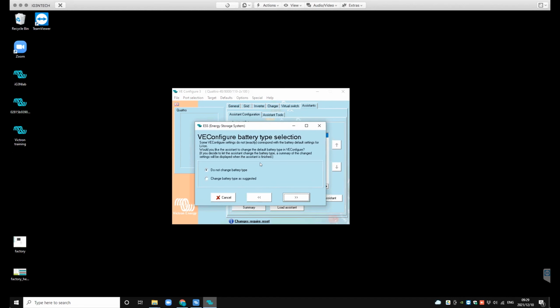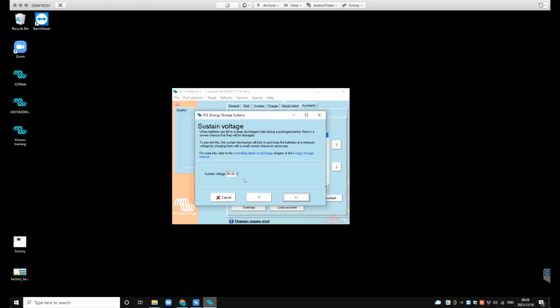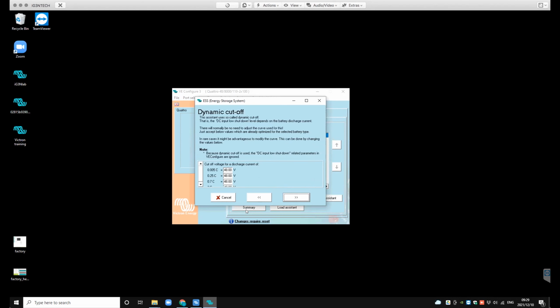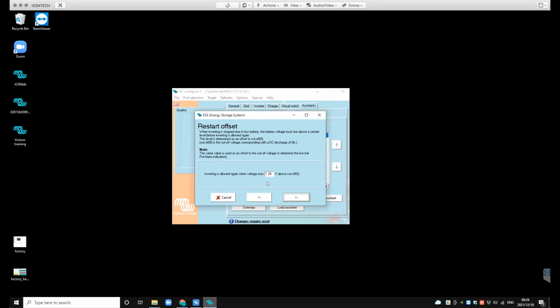We don't want to change the battery type that we saw just now under the charger. Our sustain voltage is set at default for a 52 volt or 48 volt system. Dynamic cutoffs, everything is on 48. Restart offset is also default, 1.2 volts. And you can get details on what these settings are on Victron's website also.